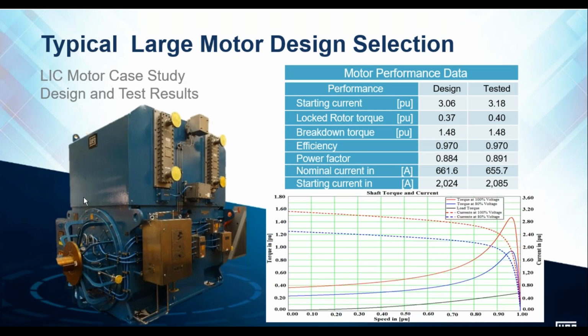Right, so this is the machine that we designed, and we created some design parameters that we wanted to meet in order to meet the requirement of the client's specification. Our starting current needed to be as low as possible without introducing any other types of starting methods. So our design was for a starting current of around 3 times. We achieved 3.18. Locked rotor torque, we wanted 0.37. We achieved 0.4. Breakdown torque 1.48, and we achieved 1.48.